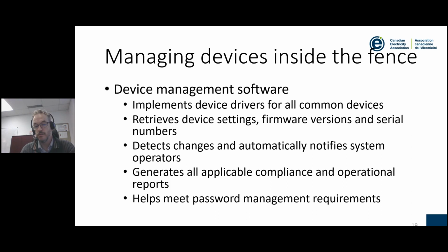Turns out that there was a very large portion of those devices that, even though the utility was sure that the passwords deployed matched whatever was in their Excel spreadsheet, in reality, for whatever reason, maybe human error during copy and pasting, they didn't match. So they were essentially stuck. Thankfully, whenever you have local access to your device, you can recuperate from that. But essentially they lost remote access to their devices, and in some critical situations it could have been quite dramatic because they thought they had access whereas they didn't actually.